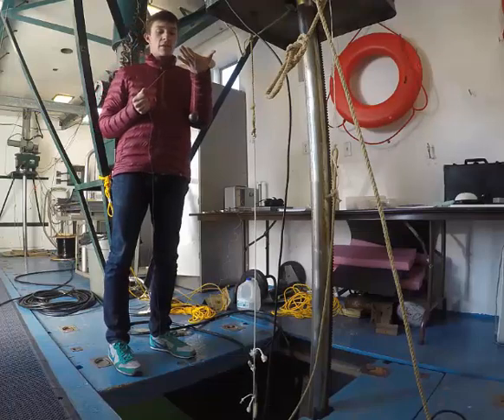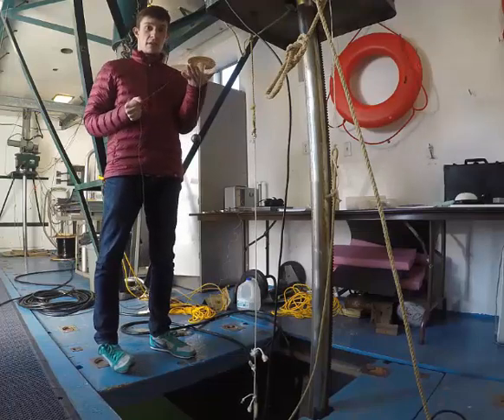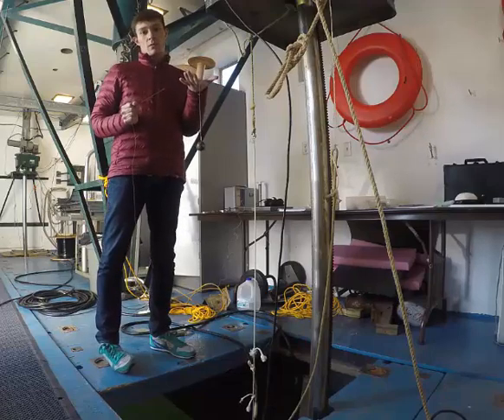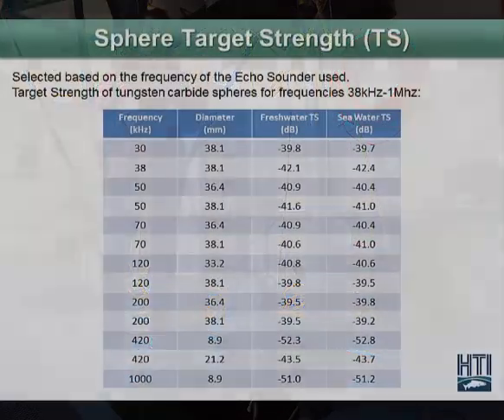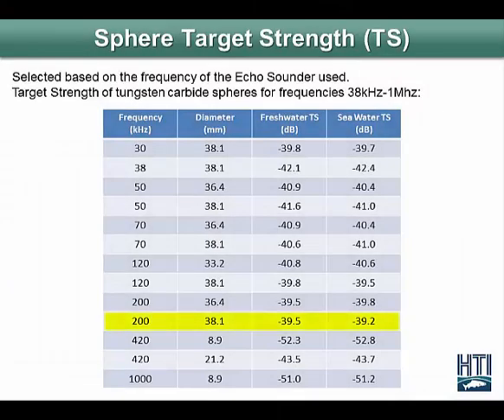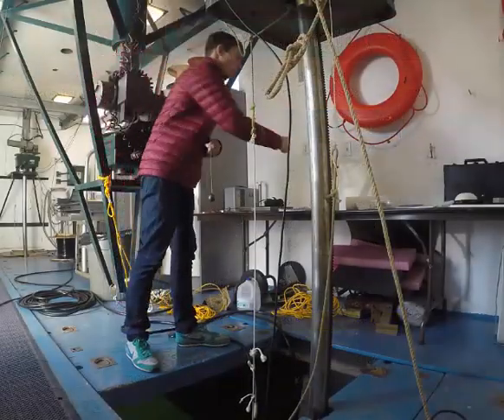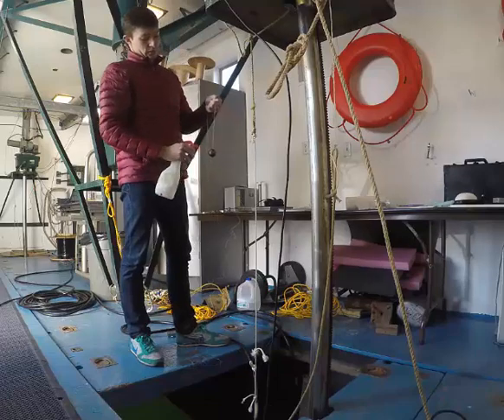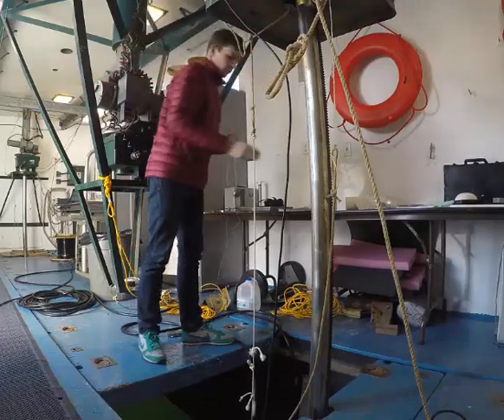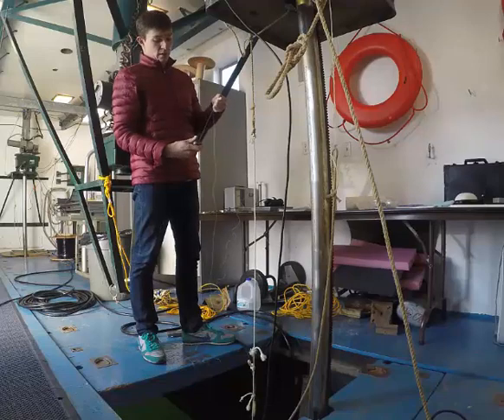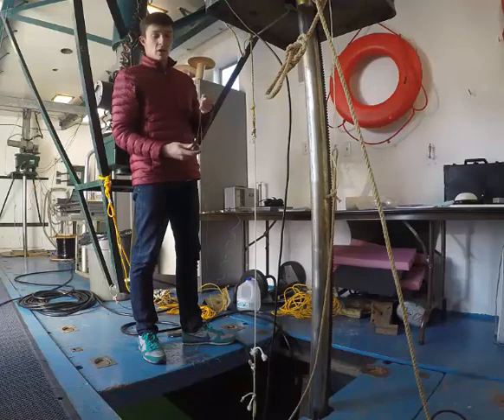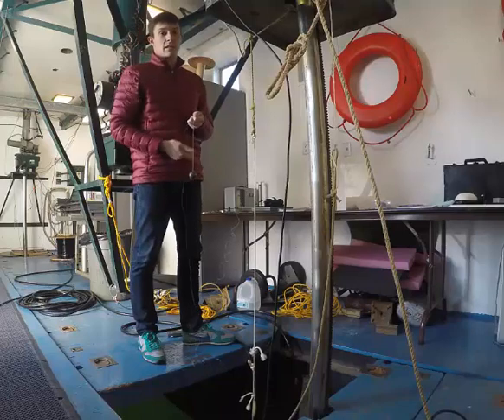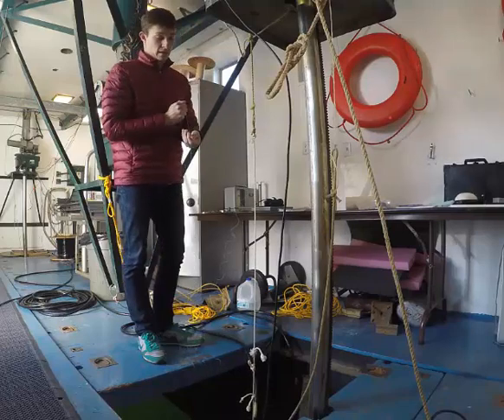The size of our sphere is selected based on the frequency of our echo sounder. We're using a 200 kilohertz echo sounder, so we're using a 38.1 millimeter sphere, which is appropriate for kilohertz ratings from 38 to 200. So as we begin our study, the first step we want to do is spray down our sphere with a little bit of a solution of dishwashing soap and water. This will remove grease and air bubbles on the sphere, which could be acoustically visible in our test.